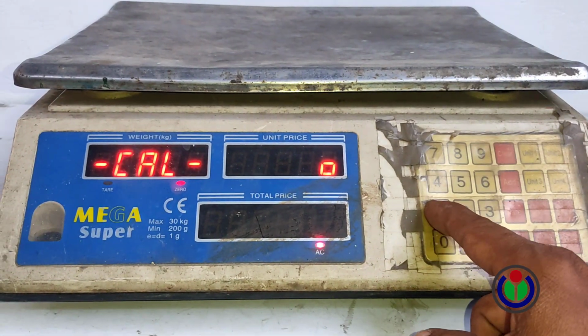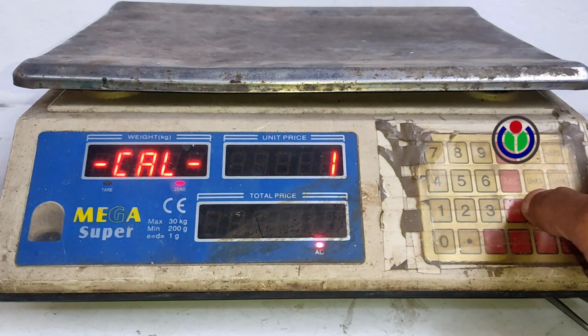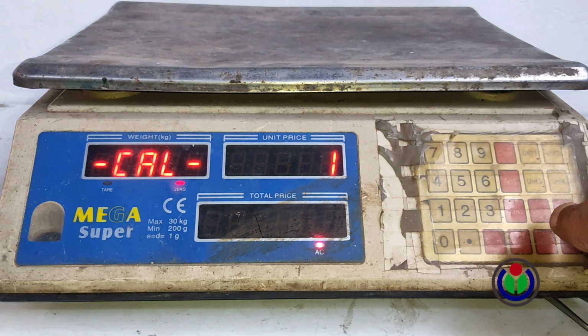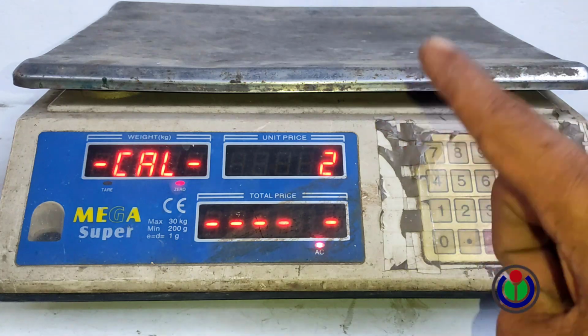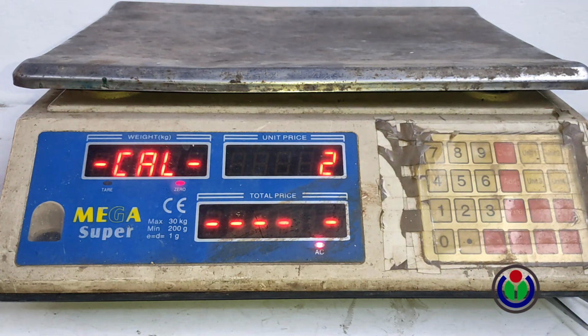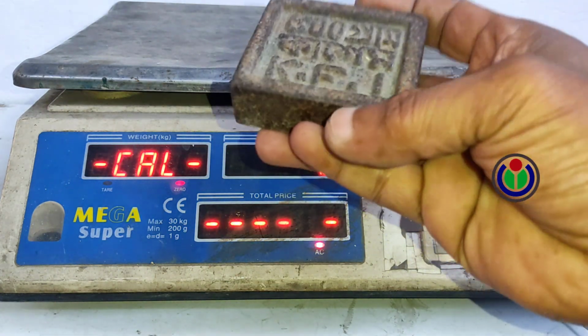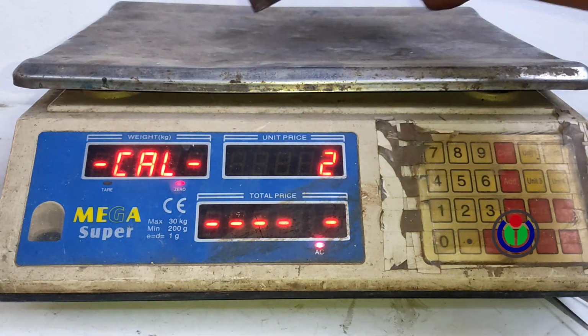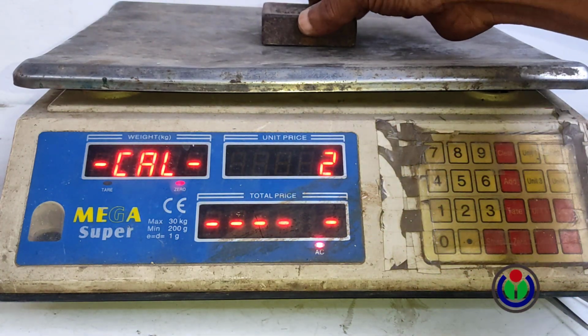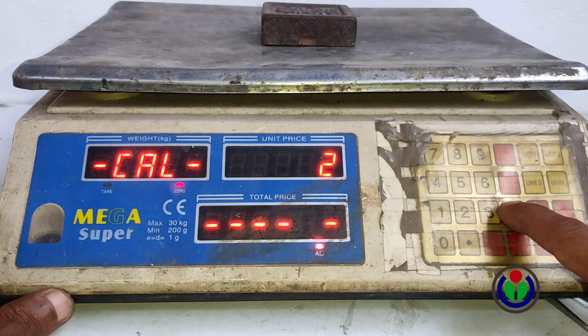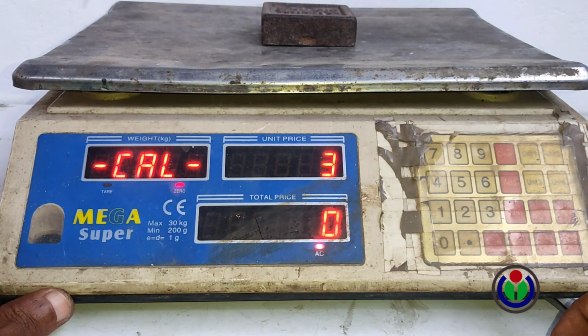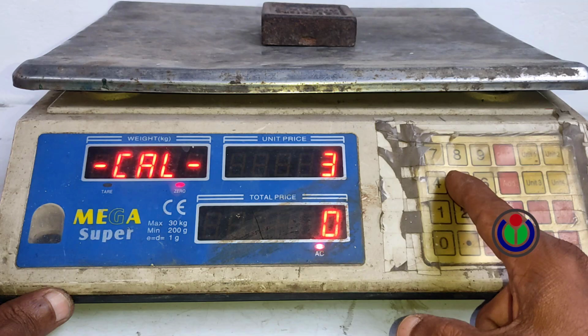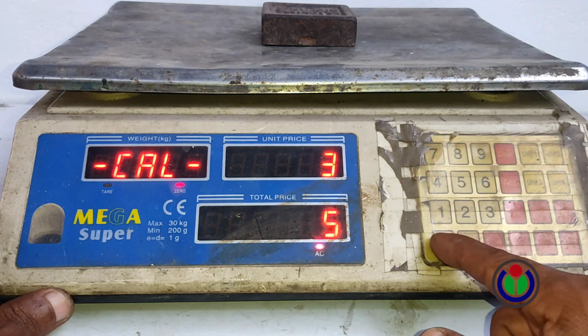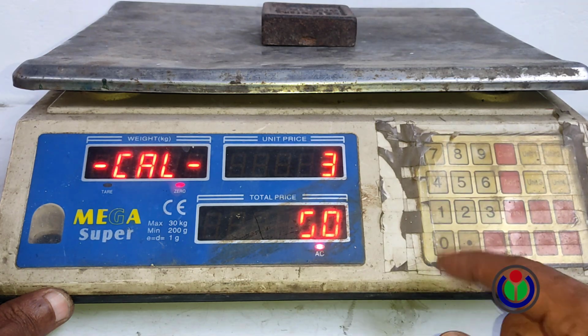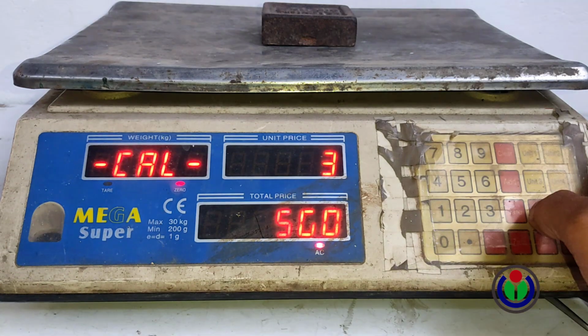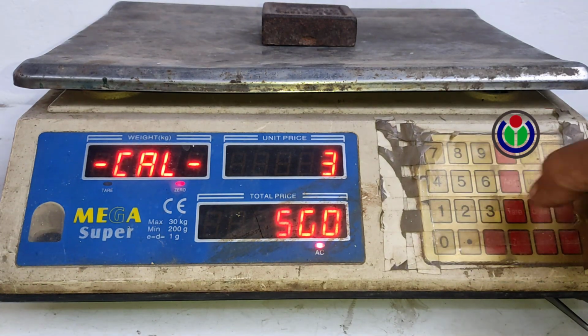Step 1. Press 1 from the keyboard, then press Tare. Step 2. When 2 is displayed on the display, a standard calibration weight set must be placed. I placed a standard calibration weight set of 500 grams. Step 3. Press Tare once, and when 3 shows, the weight of the weight set should be entered in grams by pressing the numbers. I wrote 500 grams as 500 and pressed Tare once to go to the next step.